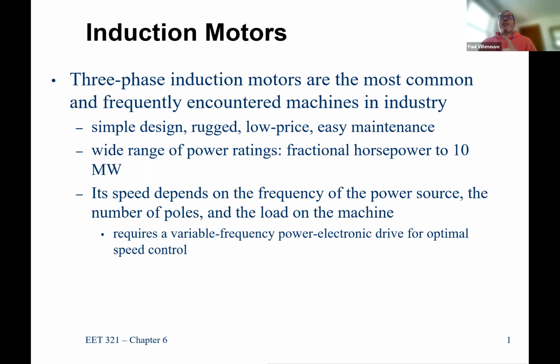So that's the primary difference between an AC induction motor and an AC synchronous motor: in the synchronous motor, you apply a DC field to the rotor, or you could use a permanent magnet motor. That's sort of the same concept. In an AC motor, it has an AC field. So DC field, synchronous machines; AC field, induction machines.